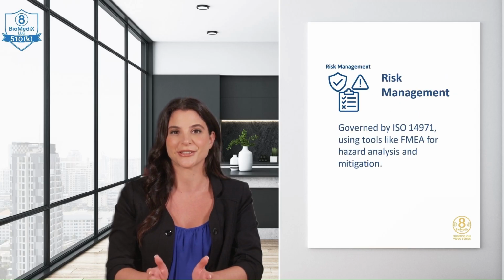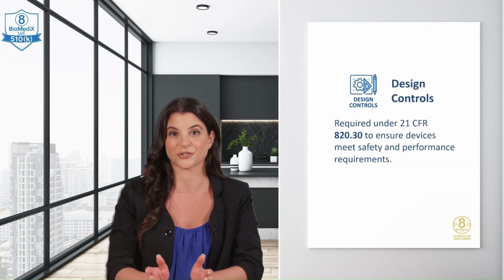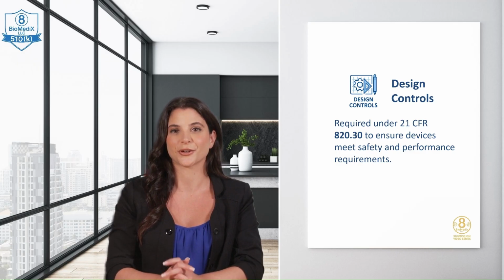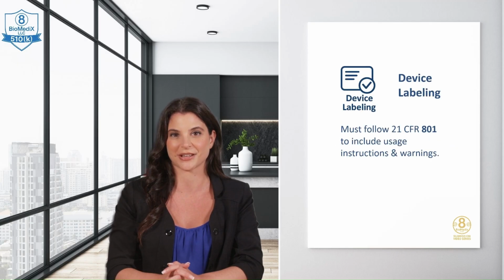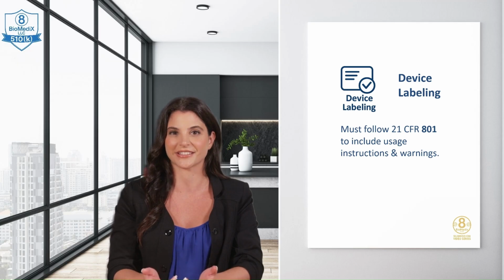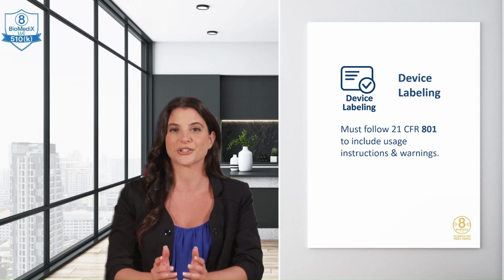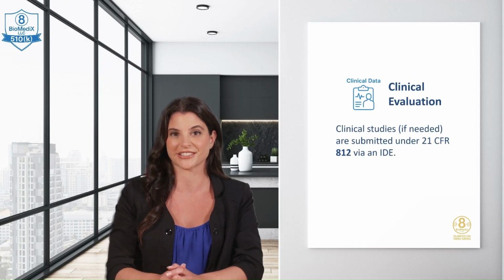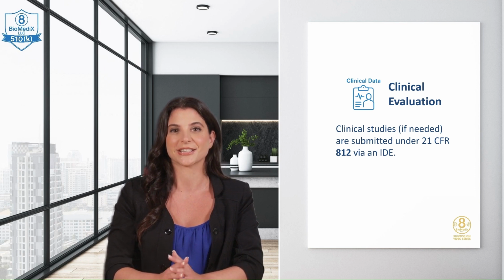Risk management, governed by ISO 14971, using tools like FMEA for hazard analysis and mitigation. Design controls, required under 21 CFR 820.30 to ensure devices meet safety and performance requirements. Device labeling, must follow 21 CFR 801 and include usage instructions and warnings. Clinical evaluation, clinical studies if needed, are submitted under 21 CFR 812 via an IDE.